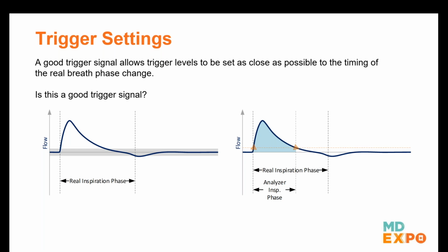The start trigger is pretty good because this signal rises very rapidly. We talk about a steep slope of the waveform. Because of that, we can set a trigger level here, this dashed line, a little bit above our gray area, where we want to avoid trigger levels because we risk false triggering. And that gives us a very accurate indication of when the inspiratory phase starts.